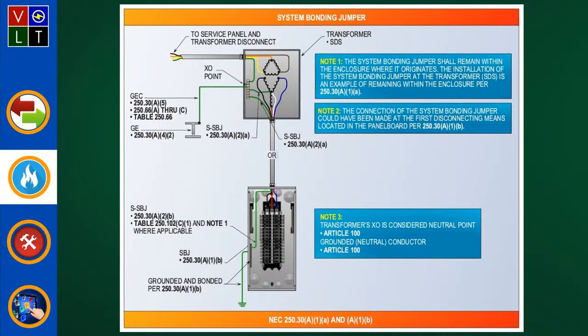Okay. Now, I'll give you an example. I'll just make a problem up. It's not in this illustration. But let's say that you had a copper system bonding jumper, and we want to know what size is required to bond and ground the secondary of a separately derived system. And let's say it has 4 3/0 THW copper conductors connected to its secondary. Well, when you go look at table 250.102(C)(1) and you pick up the 3/0 conductor, it's going to tell you the size of that bonding jumper is going to be required to be a number 4.